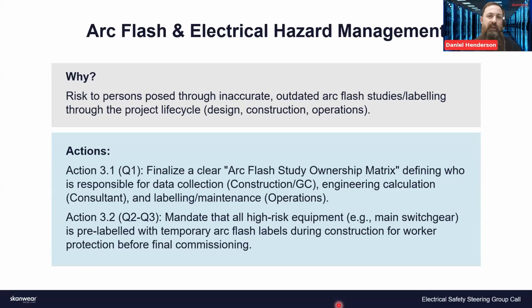That's something else to take into consideration. When we're doing that initial modeling, is it actually validated for the exact relay that's going in? Or once we've started procurement and know what relay is going in, is the model then updated to reflect the relay type, whether it's ETAP, SKM, DIgSILENT, or whatever software, to make sure once it's actually in place, we can put those settings in? Often we can't, if it's not possible within the electronic relay settings.